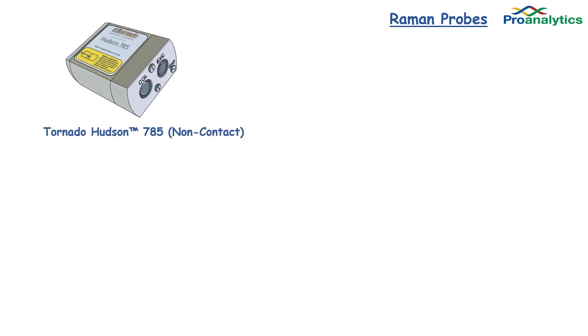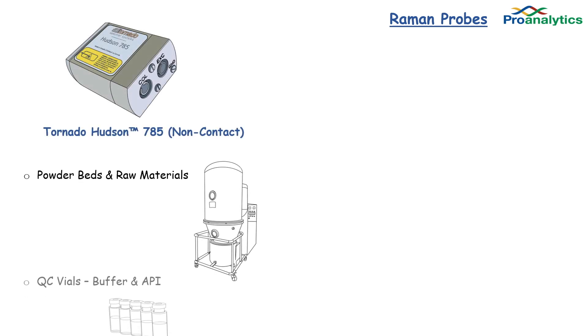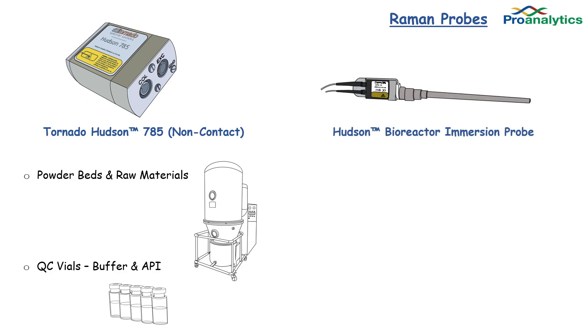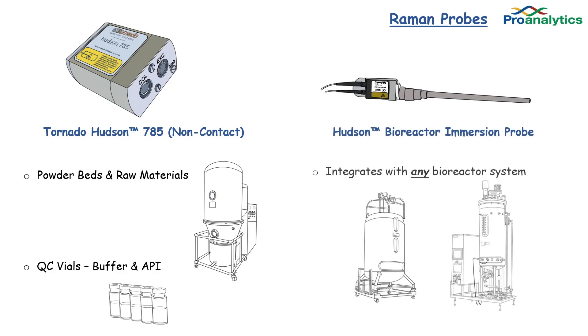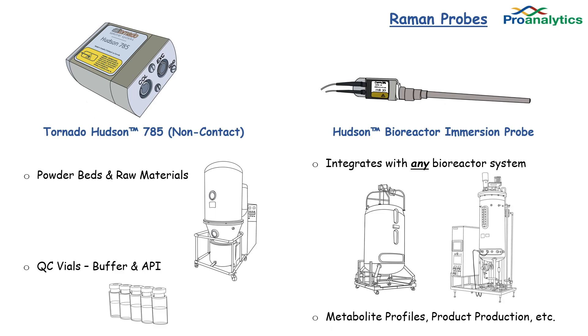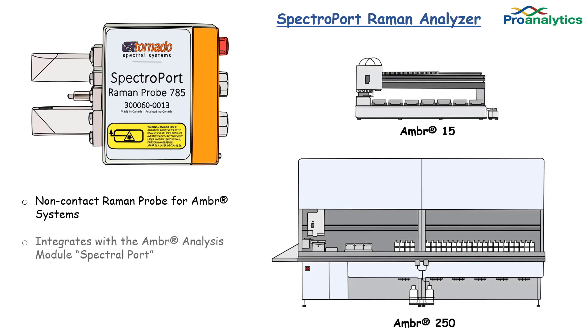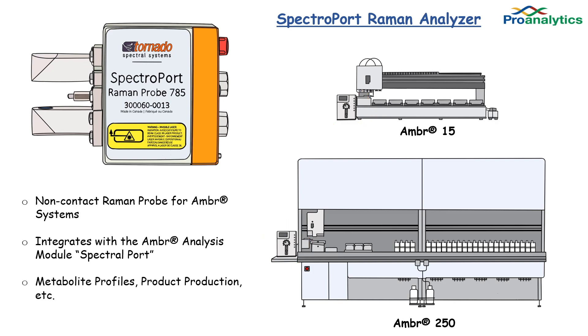Let's look at the non-contact and contact Raman probes. The Tornado Hudson 785 is a non-contact Raman probe for the analysis of powder beds or raw materials such as salts and media components. It can also be used with vials to examine the quality of your product. The Hudson Bioreactor Immersion Probe works with glass, stainless steel, or single-use bioreactors for real-time product or metabolite analysis. The Spectroport Raman probe pairs with the Sartorius AMBER systems, plugging directly into the AMBER analysis module to view metabolite or product profiles.